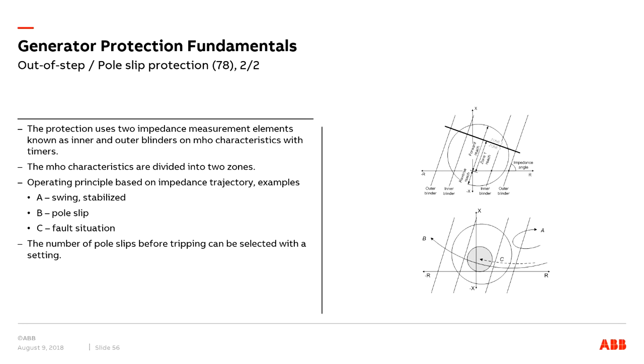the power swing situation. A is a situation where there's a power swing, but the system is stable. So in a power swing situation, the locus will not enter the operating zone of the protection. And B is a situation where there's a pole slip, where the impedance locus enters the operating region and then moves out. Okay, and C is an impedance locus where there is a fault situation, which goes and stays inside here. So we can detect the pole slip or out of step condition based on this locus of the impedance.